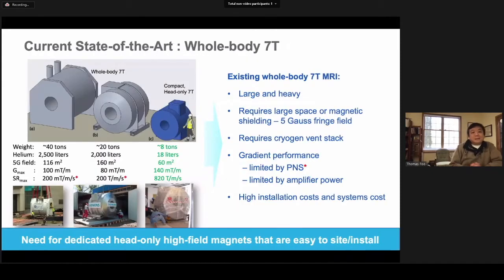High field magnets today are characterized by very large and very heavy magnets weighing anywhere from about 20 tons to 40 tons. They consume a great deal of liquid helium, have a very large 5 Gauss line that places limits on where they can be installed, and require a vent stack, just in case the magnet quenches, to accommodate the liquid helium that expands over 750 times. And because these are whole body systems, the gradient performance is limited. They're limited by PNS in terms of how high a slew rate you can achieve, and also limited by gradient amplifier power in terms of the maximum gradient amplitude that can be achieved. All of this leads to very high installation costs and total system costs.